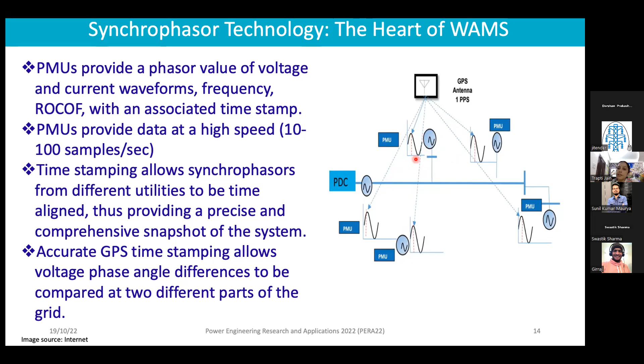These voltage phase angles are basically an indicator of the stress on the system. Earlier, using state estimation, we were getting voltage magnitudes, current magnitudes, and power and reactive power measurements. From those measurements we used state estimation to obtain the phase angles of the voltage at different buses. Now we directly get the phase angles at all these buses. One bus becomes the reference, and you can monitor these phase angle differences easily, which reflect the stress on your system. So it becomes quite easy to monitor these things.